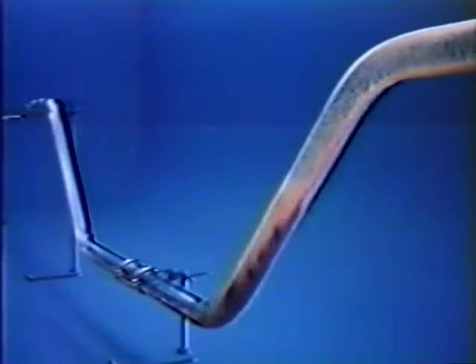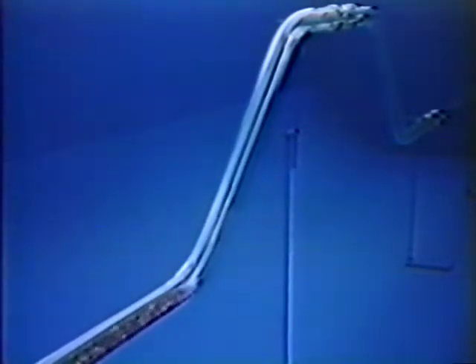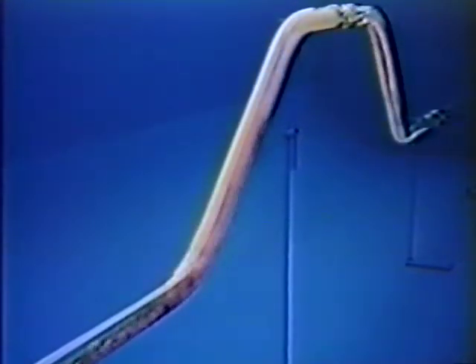In a lot of places, the gas pipelines dive under rivers and canals. At low gas velocity, liquid can accumulate in these crossings. In autumn, when the gas offtake rises, the gas velocities increase, creating conditions likely to give rise to liquid being blown out of these crossings in slugs. At gas velocities in excess of about 4 meters per second, the condensate flows through the crossing without any difficulty. Liquid is also likely to accumulate upstream of dike crossings and can then be carried along by the gas when its velocity increases.